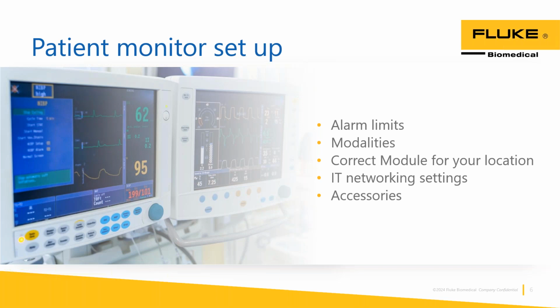100%, man, 100%. And actually, I'll even take that one step further. Another common thing I see happen is people have a set of test leads, because they know if they go find a good set of ECG leads and a good non-invasive blood pressure hose and all these other things, when they go out and do the procedures, then they know that those are good working sets. So if they're going to find anything wrong, it's going to be with the monitor, not with the cables. But by doing that, we kind of remove that step of checking for leak tests. Like when you change out those hoses, if you're using the same test set every time, you might not find that the hose attached to that non-invasive blood pressure monitor may have a slight leak.